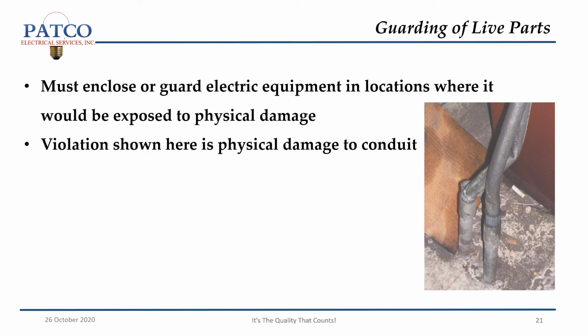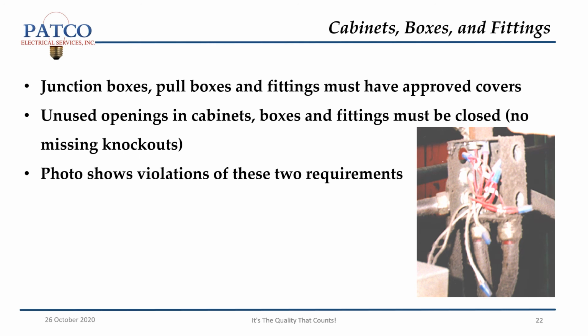Guarding of live parts. You must enclose or guard electric equipment in locations where it would be exposed to physical damage. A violation shown here is physical damage to conduit. Cabinets, boxes, and fittings. Junction boxes, pull boxes, and fittings must have approved covers. Unused openings in cabinets, boxes, and fittings must be closed. No missing knockouts. The photo shows violations of these two requirements.